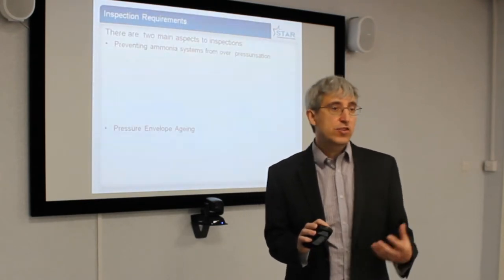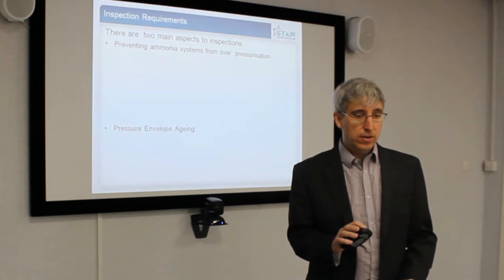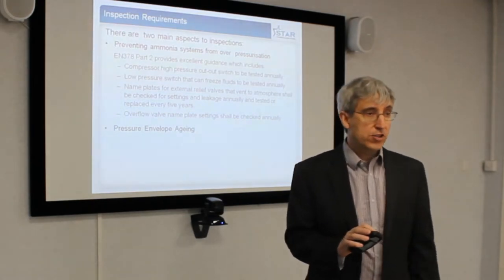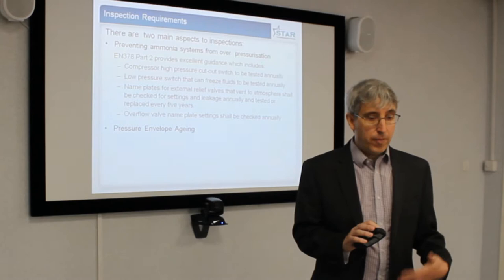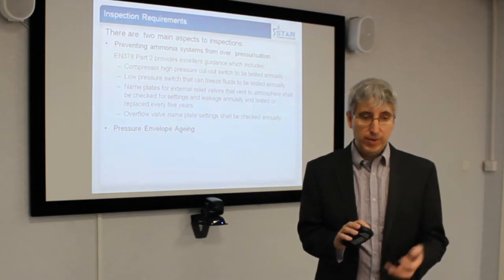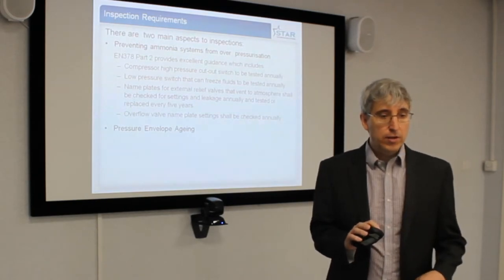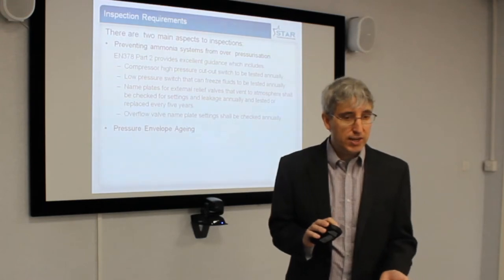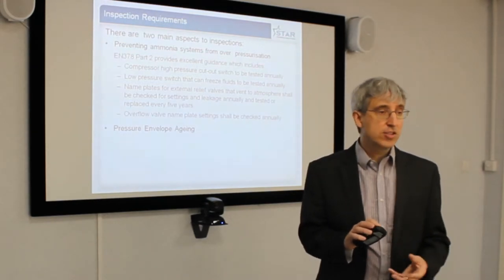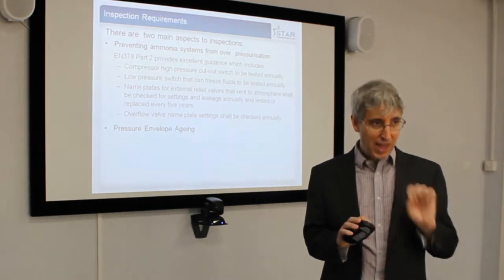There are really two types of inspection requirements: preventing ammonia systems from over-pressurising, and pressure envelope aging. EN 378 Part 2 gives detailed requirements: compressor high pressure cutouts to be tested annually, low pressure switches on freezing fluids to be tested annually, name plates on relief valves to be checked for appropriate settings, and relief valves to be replaced or recalibrated every five years. It is very detailed — there is no getting away with it, it is black and white.